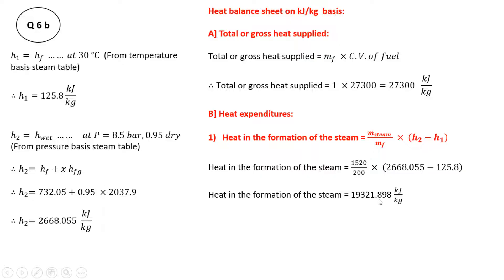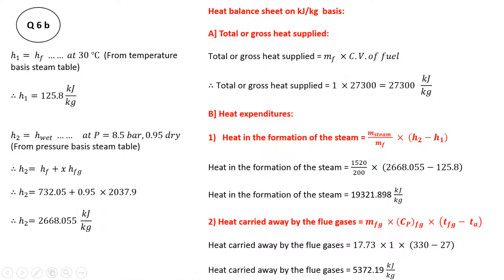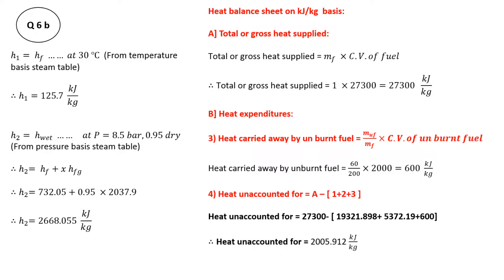Next, we find the heat carried away by the flue gases using Q = m·CP·ΔT. Mass of flue gases is already given per kg of fuel burned as 17.73 kg, specific heat of flue gases is 1 kJ per kg Kelvin, temperature of flue gases is 330 degrees centigrade, and boiler room temperature is 27 degrees centigrade. Therefore, heat carried away by the flue gases comes out to be 5372.19 kJ per kg.